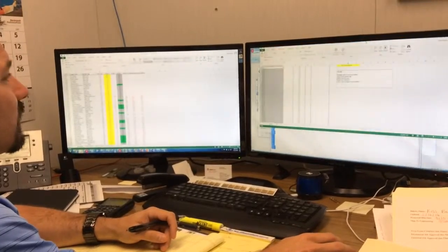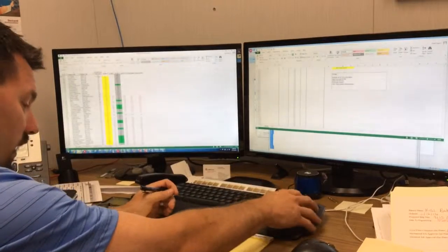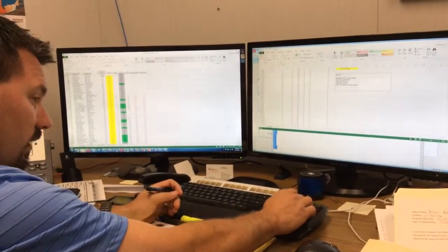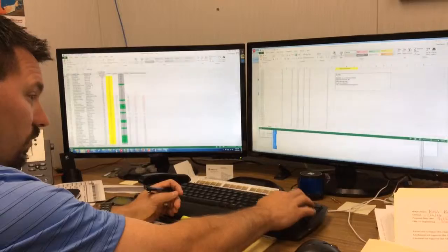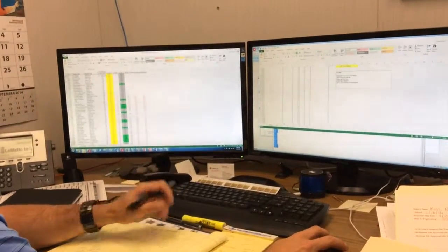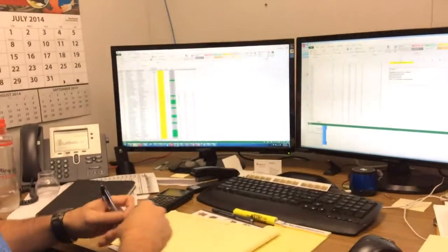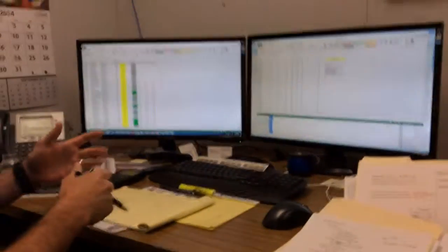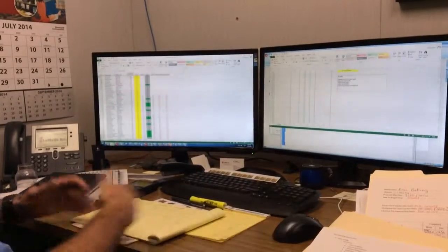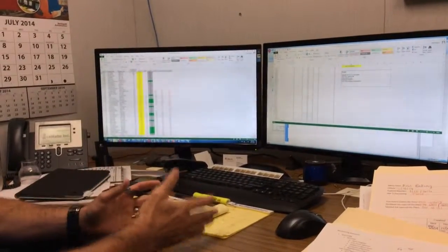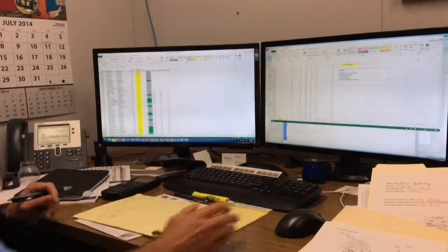Yep. After I have that, I come back to my terminations sheet and plug in my numbers for KISS: 898, 364, plus 240. It's a total, because these are all the wires that are going to have to be pulled. So we've determined that if I have a total of 1,500 terminations, with a rate of 0.92 per termination, that backtracks and gives me the estimated hours that it's going to take for wire pull. Good. Cool. All right, stop.